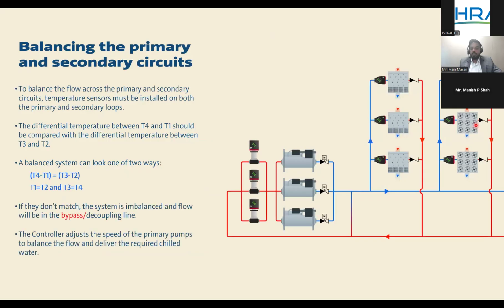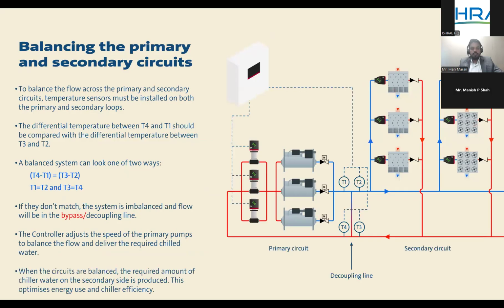So let's see quickly how the balancing happens between primary and secondary. As I said, this is the decoupler line. We capture the temperature across the decoupler line on both supply and return, T1, T2, T3, T4. Four temperature sensors are installed across the decoupler line. And ideally speaking, when the system is balanced, where the supply meets the demand exactly, the T1 temperature is equal to T2 and the T3 temperature is equal to T4.